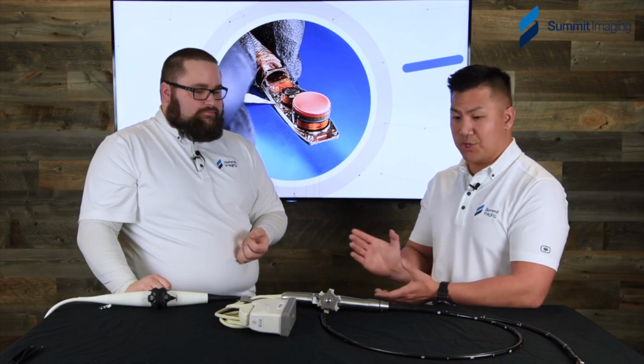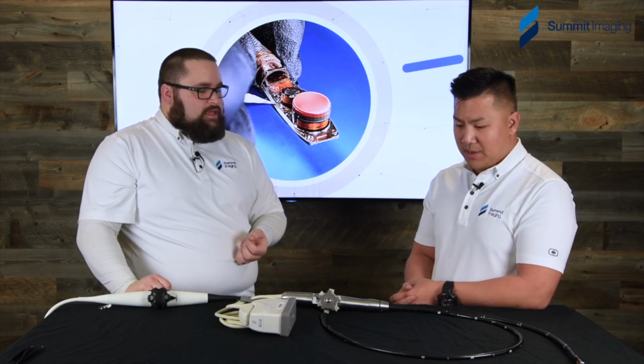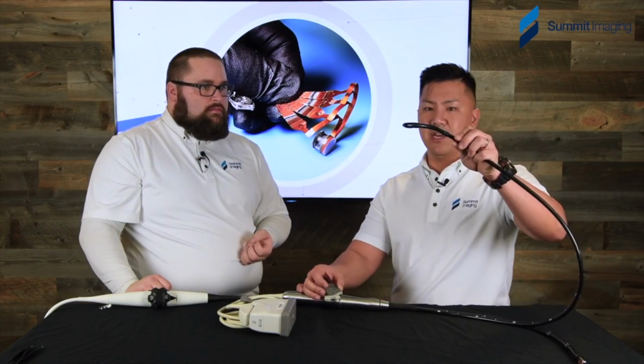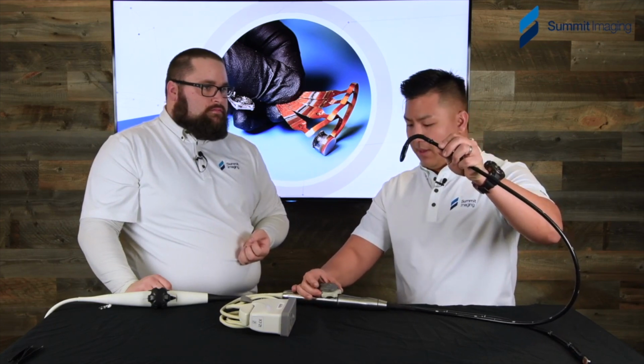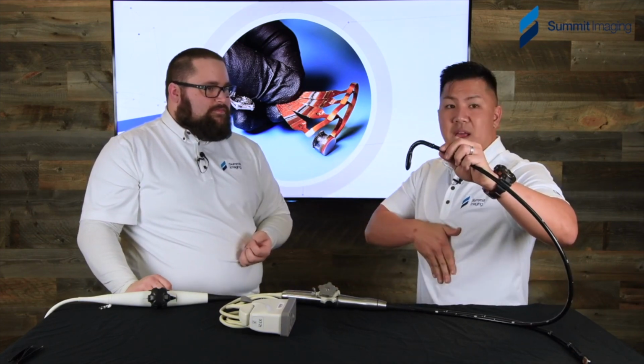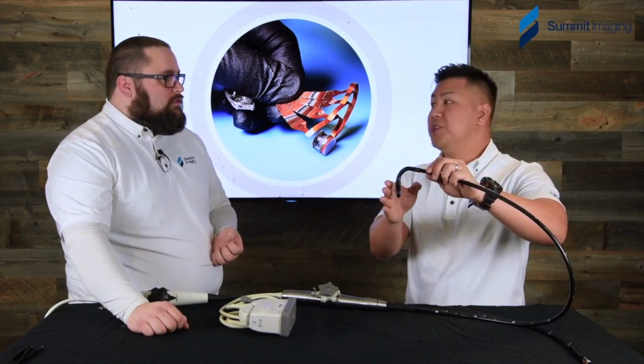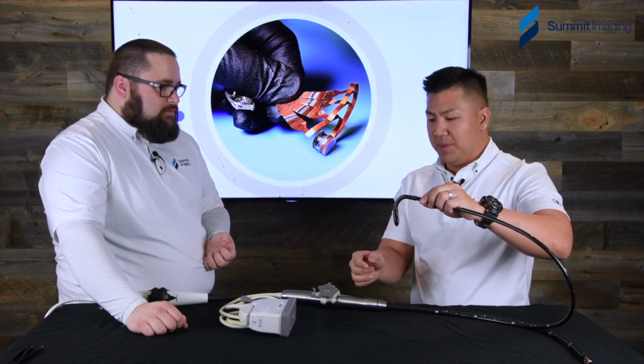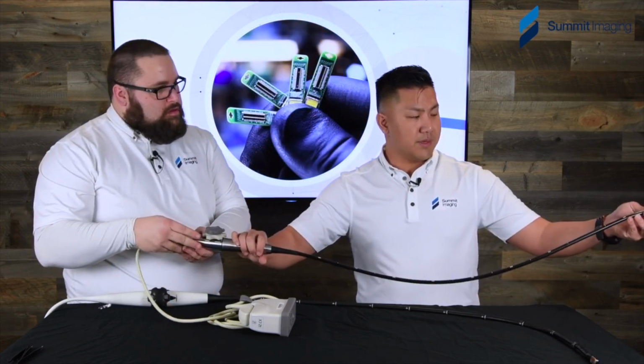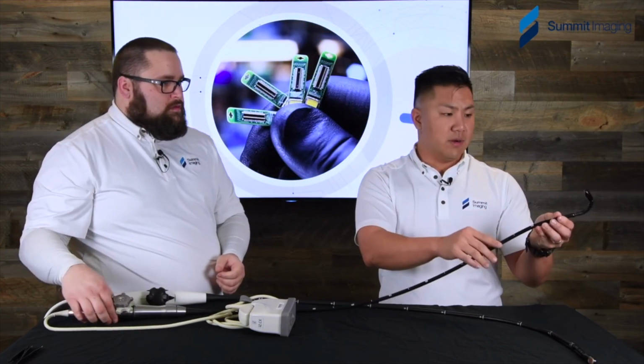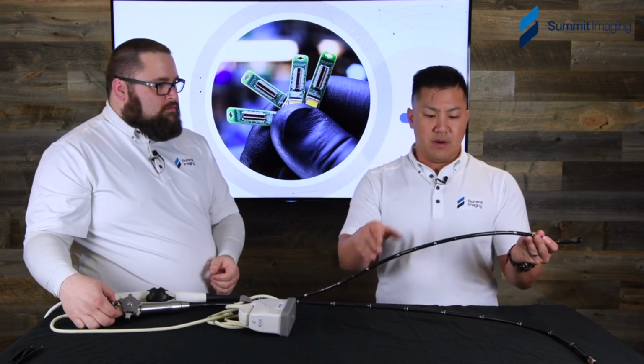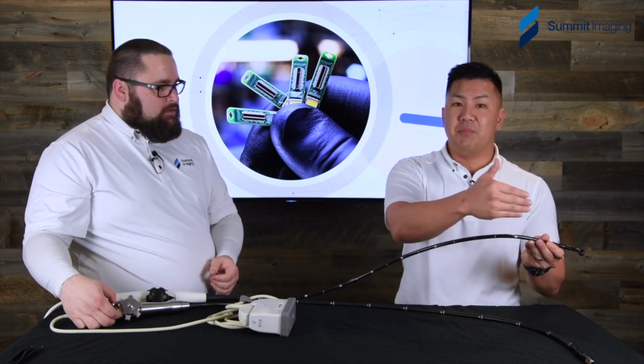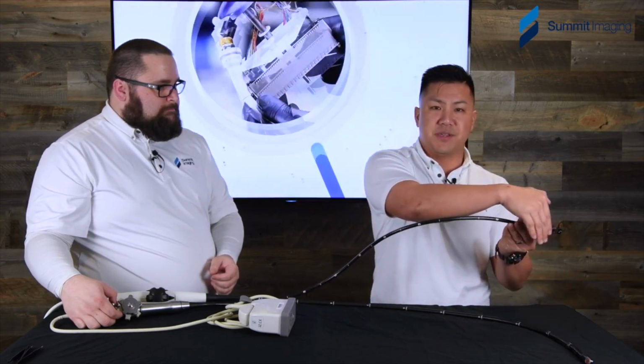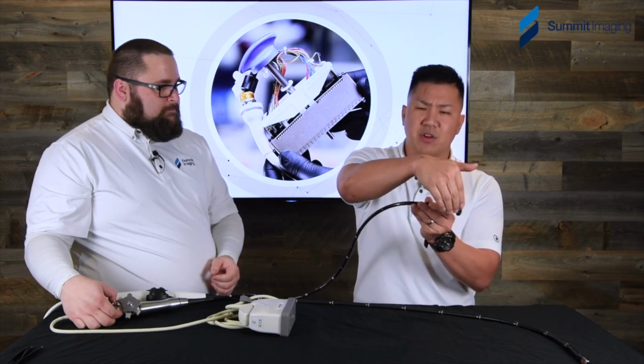Those are both very bad issues, because then you've got cross-contamination risk. And I think the other one was you discovered that on these TEE probes in particular, you can actually lock them, and this is to apply pressure inside the esophagus to get the best image possible of the heart. But when these are pulled out of the esophagus, when you lock this probe to get the best image of the heart, when this is pulled out, the bite guard may be up front, but the molars in the back, because it's locked, this will be hitting the back of the molars and just dragging across all those teeth.